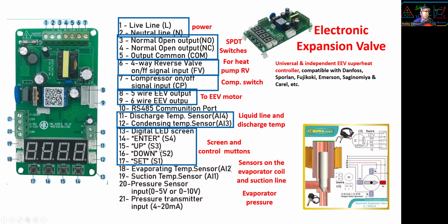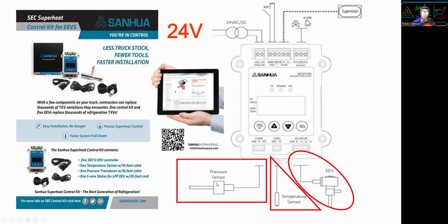And we have this is the screen up and down, left and right, and evaporator temperature, and suction line temperature, both. One sensor inside the evaporator to measure about 1/3 into the evaporator, or 2/3 out, excuse me. That's probably for freezers, and suction line temperature. Then pressure sensor and another extra pressure sensor. And communication port number 10. Alrighty, enough of this, pretty much the same thing. This is another one. Sensor, temperature, pressure, temperature, and valve.